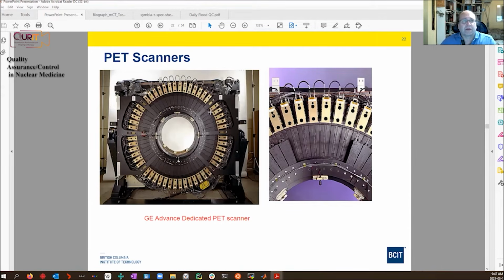So this is an older camera, but I've got a nice cutaway of it. This is an old GE Advance. So in here is a block detector, which consists of one cut-up block of scintillator cut into smaller sections, which have various names, like some people call them crystals, some people call them fingers or detector elements. We'll talk about these in a minute. This technology of one cut crystal, and you use 4 photomultiplier tubes to identify from the pattern of light which crystal was hit.